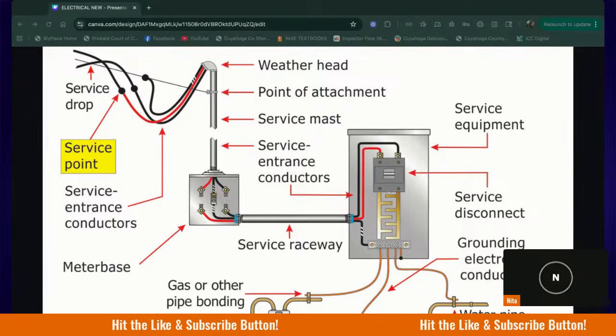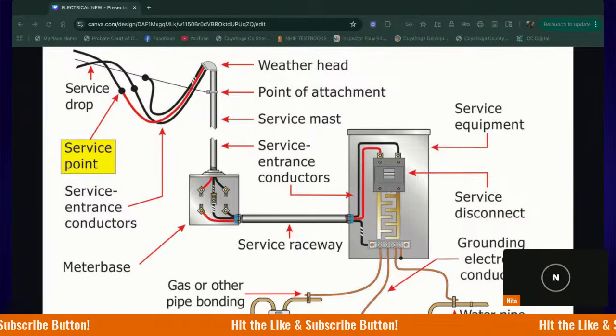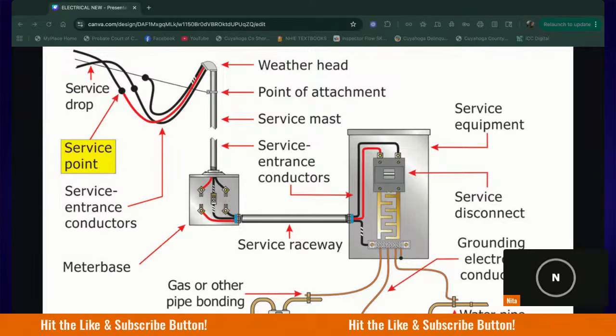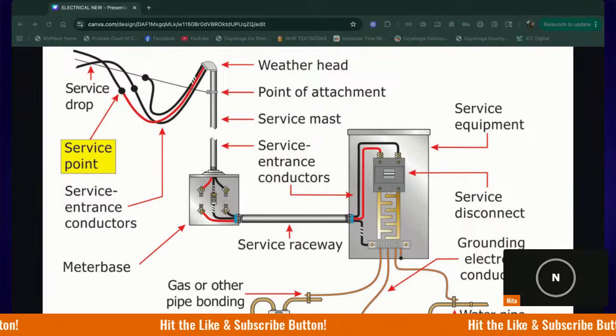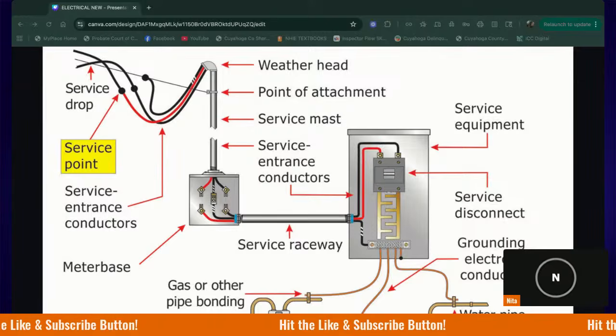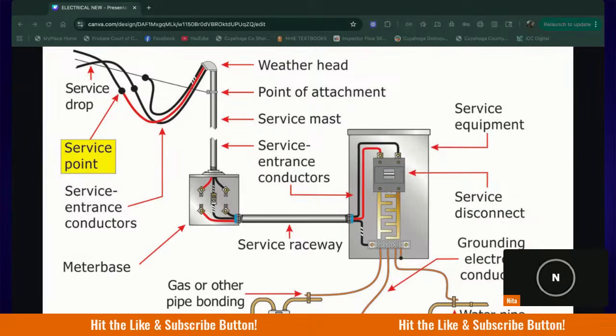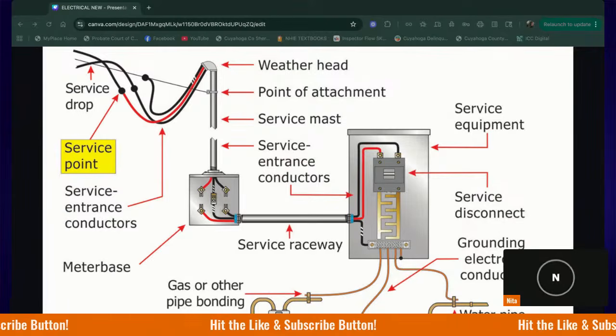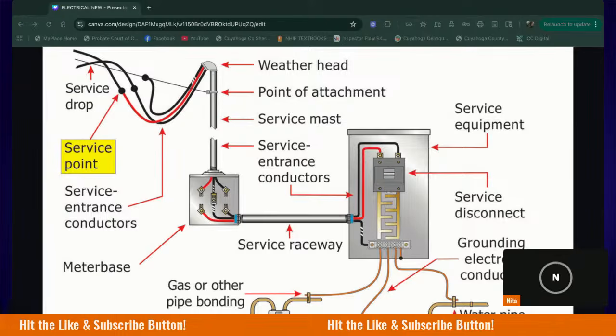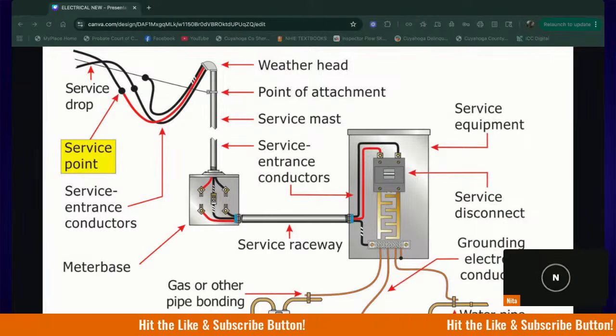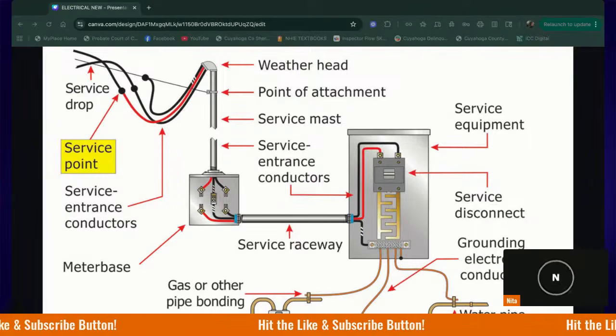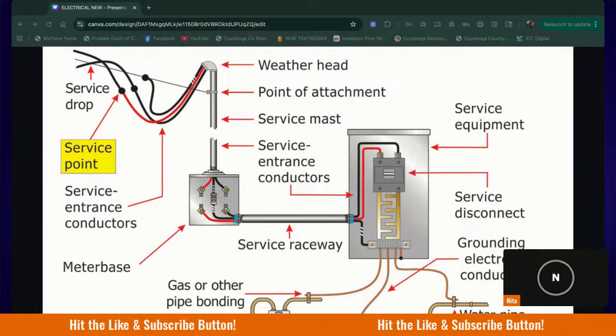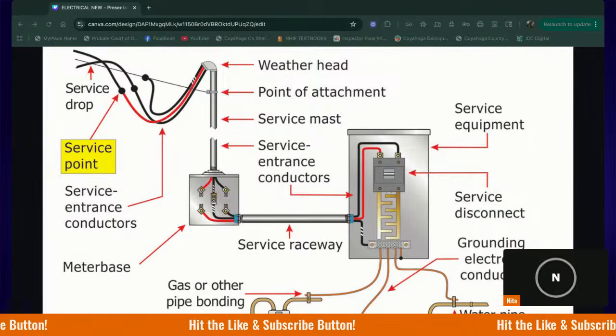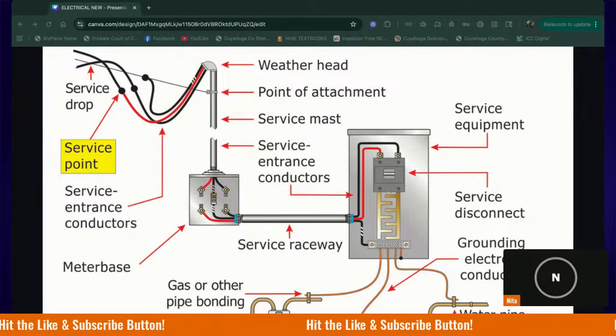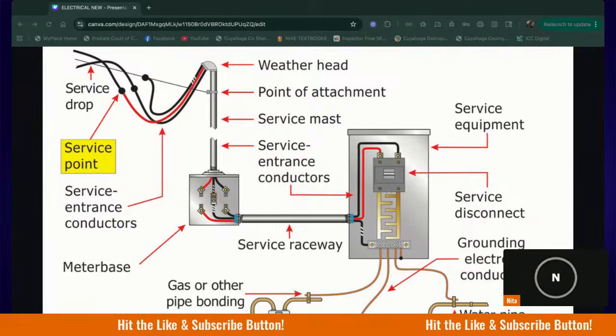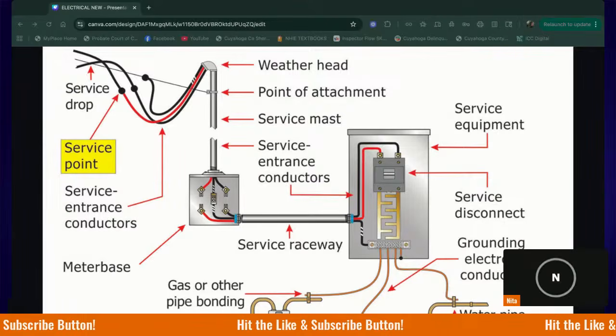But from here, our conductors travel down through the service mast, which looks like a tube. It's conduit that's protecting our service cable, which are 2 hots and our neutral, protecting it from the elements. Okay, so now I'm at step 5. Luis, I can see you now. What happens at step 5? It goes to the meter base. Yes. The utility meter base measures the electricity to charge the homeowner. That's absolutely correct. So this is our service mast. This is our meter base, which contains our meter.